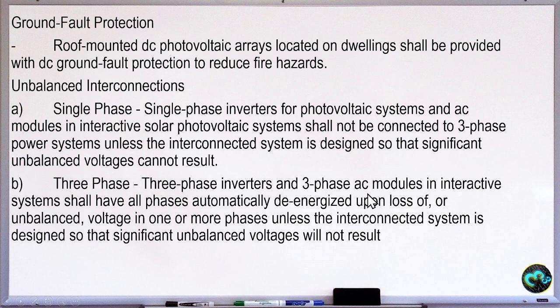Three-phase. So three-phase inverters and three-phase AC modules in interactive system shall have all phases automatically de-energize upon loss of or unbalanced voltage in one or more phases unless the interconnected system is designed so that significant unbalanced voltage will not result. So in case na three phase yung module tapos three phase din yung system na i-connect mo, they must have unison na in case magkaroon ng problem, magkaroon ng isang phase na walang voltage, automatic na mag-disconnect lahat. It will allow din siya as long as the power system itself has a design na kahit magkaroon ng unbalanced voltage, it will have its own mechanism to prevent such unbalance to occur.